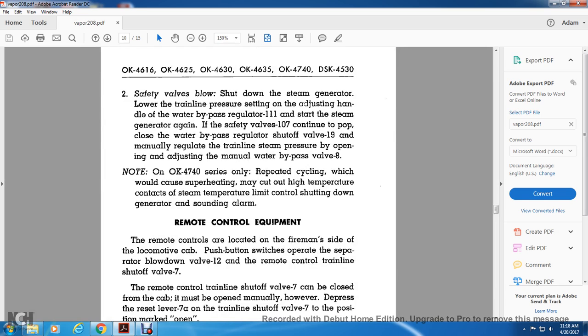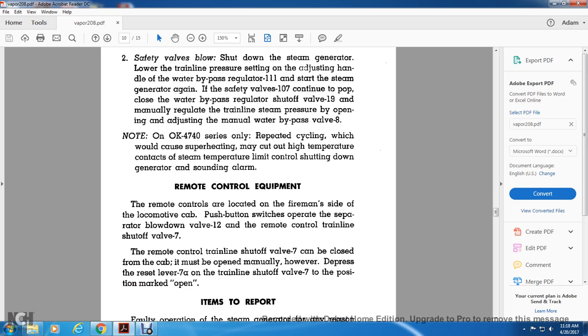If safety valve 107 continues to pop, close the water by-pass regulator shutoff valve-19 and manually regulate the trainline pressure, opening and adjusting the manual water bypass valve 8. Note that on the OK 4740 series, a repeating cycle which would cause superheating may cut out the high temperature contact steam temperature limit control, shutting down the generator and sounding the alarm.